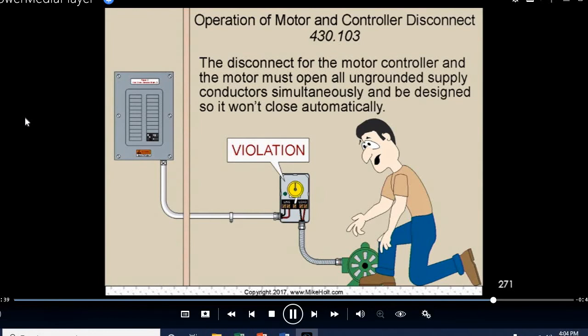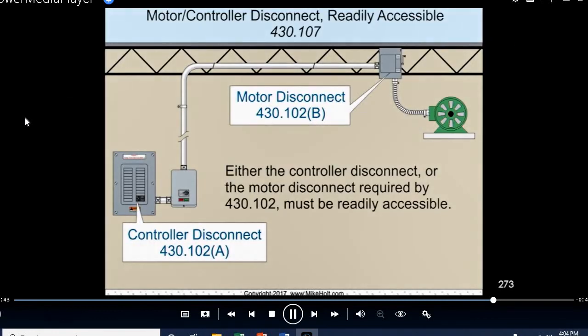Brian, let's make a note that there's resolution on this graphic here. Now, the readily accessibility. I like this. I think this is what we should be doing with switches. When rules have disconnecting means, they should tell us what to do with the readily accessibility. We saw that in the electric space heating, it had to be what? From a readily accessible place. This one says either the controller disconnect or the motor disconnect required by 430.102 must be readily accessible.